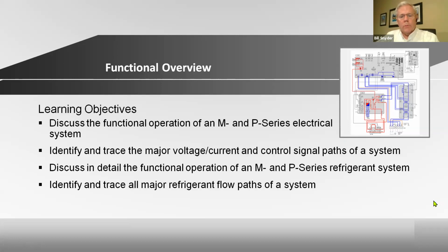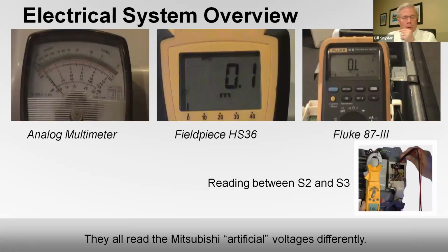We're going to talk about some wiring and some piping and some different things, but first of all, let's start off with earlier sessions, where I talked about S1, S2, and S3. S1 and S2 are your line voltage between your indoor and outdoor unit. So across those, you should read 208, 230 volts. And between S2 and S3, you're going to get a DC volt. It's kind of an artificial voltage. It's communicating back and forth, kind of in a DC signal.